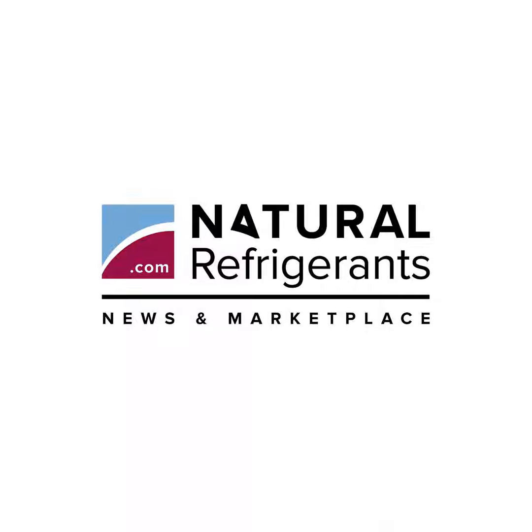Of that, up to 4 megawatts, 1,137 tons of refrigeration, of waste heat can be recovered and supplied to nearby CERN buildings for space heating. CERN, Jaeggi, and Austrian refrigeration contractor Equans collaborated on the project.